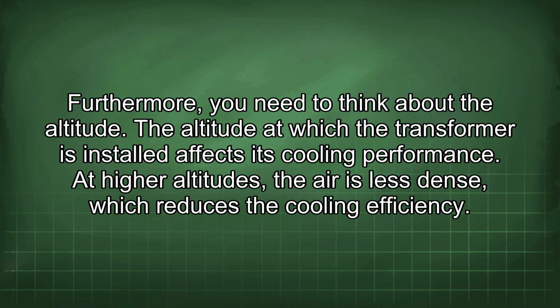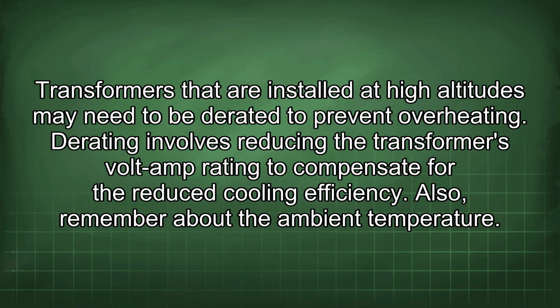Furthermore, you need to think about the altitude. The altitude at which the transformer is installed affects its cooling performance. At higher altitudes, the air is less dense, which reduces the cooling efficiency. Transformers that are installed at high altitudes may need to be derated to prevent overheating. Derating involves reducing the transformer's volt-amp rating to compensate for the reduced cooling efficiency.